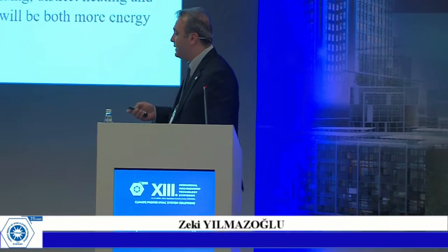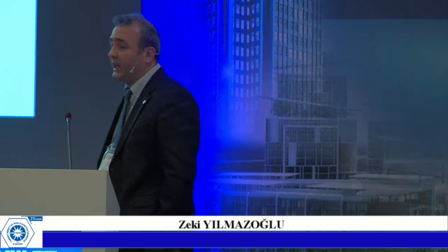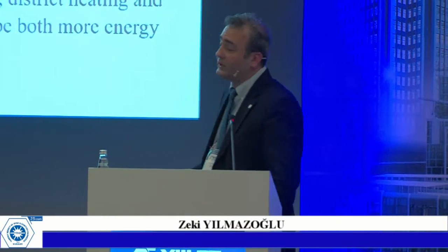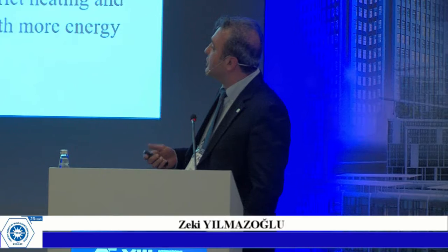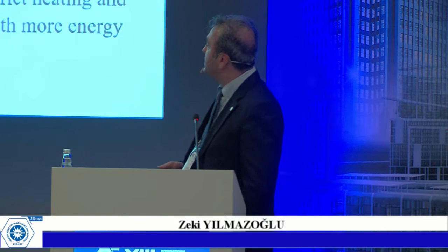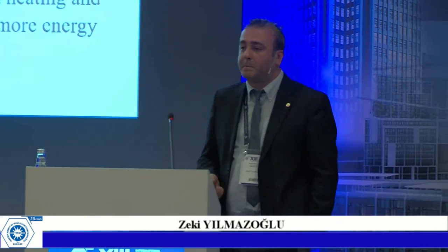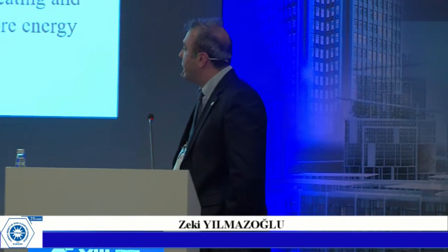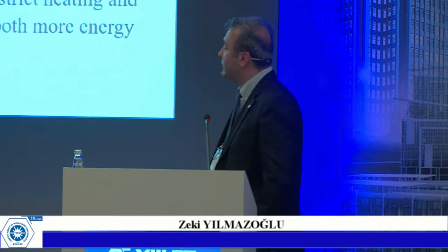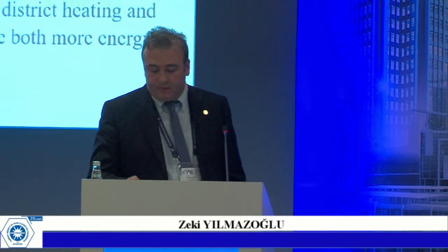If I say the conclusions: accumulation of emissions among the buildings, on the breathing zone, or the fresh air intake of mechanical ventilation on the leeward wall of the tall building, poses a health risk for the staff and inpatients. Although the use of such systems in urban areas has many positive results in terms of energy efficiency, the dispersion of emissions among the buildings and the identification of critical areas must be regulated. Rather than considering a discrete system for each building, district heating and cooling of regions with correct urban region planning will be both more energy efficient and healthier for the residents.